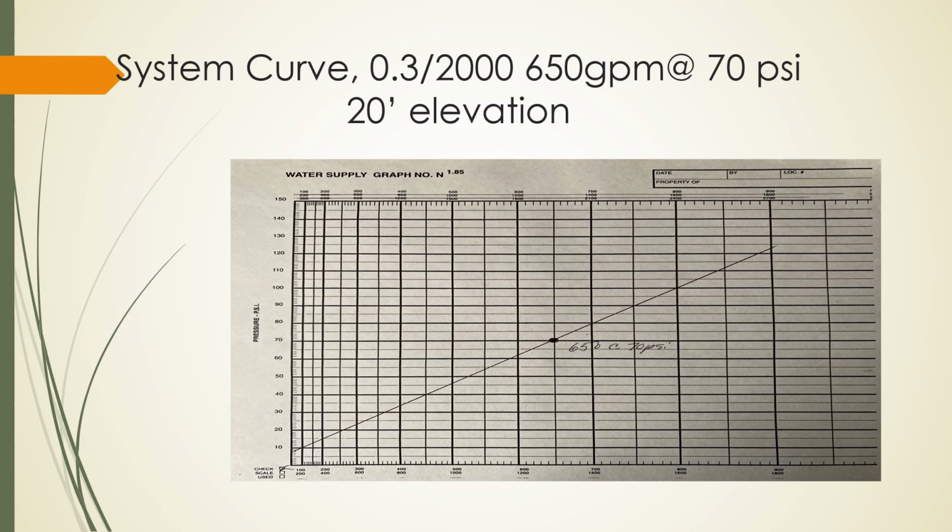When you get a sprinkler head, for instance, you'll notice that there's a K factor associated with it, 5.6, 25.2, etc. Well, we can reduce the configuration of piping and the outflow through sprinkler heads to a K factor as well. And that's what we're doing with this particular graph. We're reducing the entire configuration of the sprinkler system to a K factor. And what we're able to do is slide up and down on that curve using that K factor.